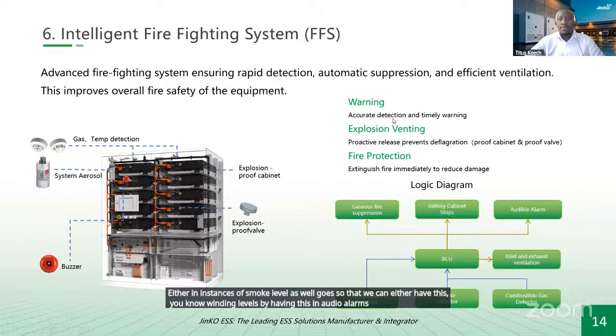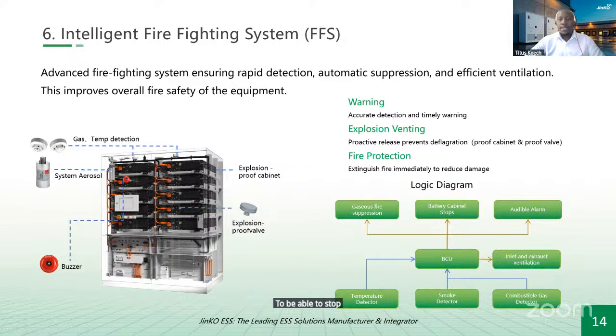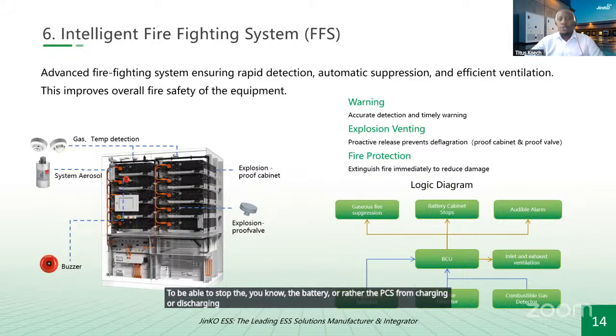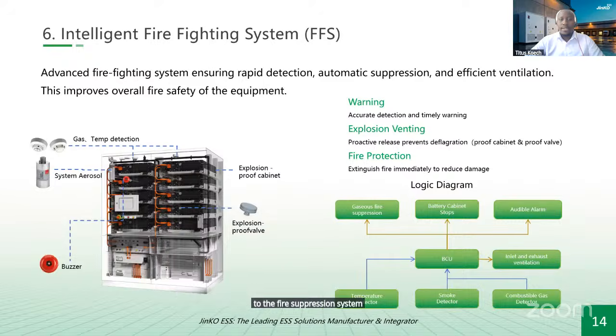We can also have these warnings stop the battery or the PCS from charging or discharging, and activate the explosion venting mechanism, or have the temperature and smoke sensors send a signal to the fire suppression system automatically.